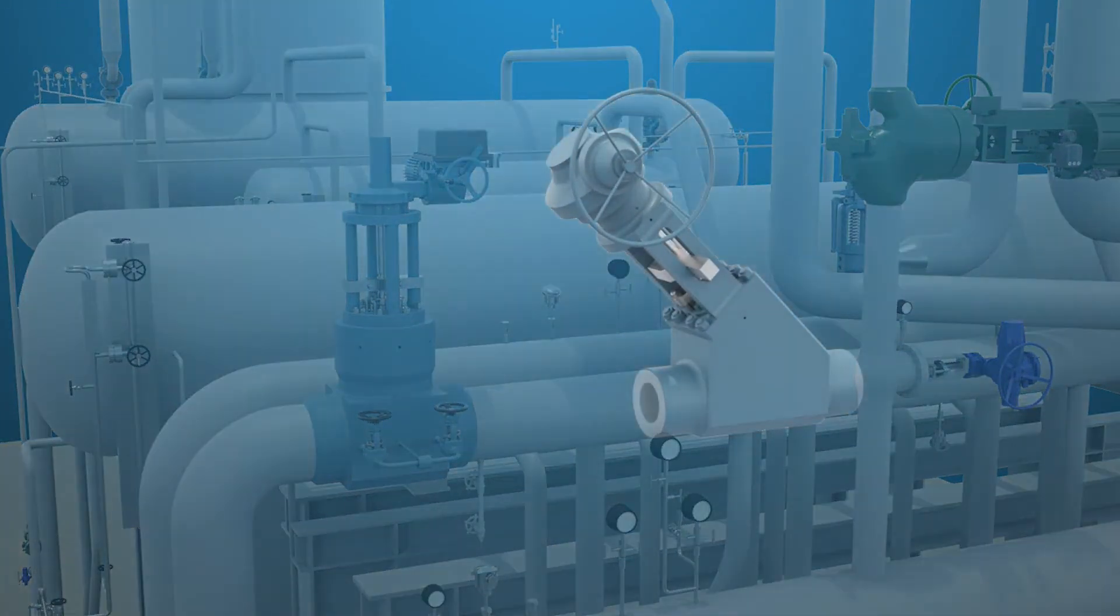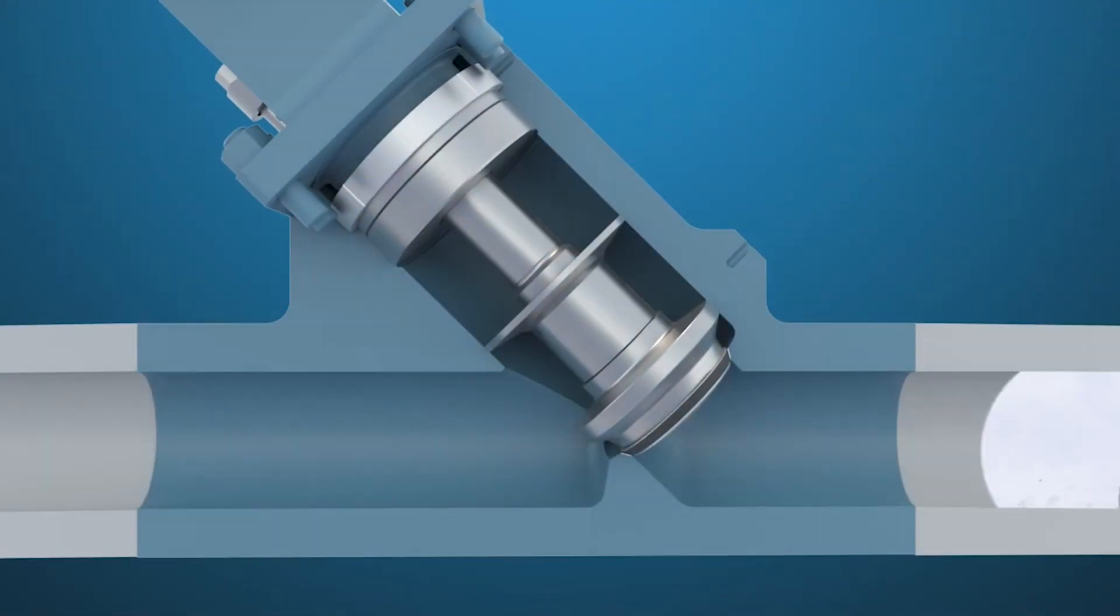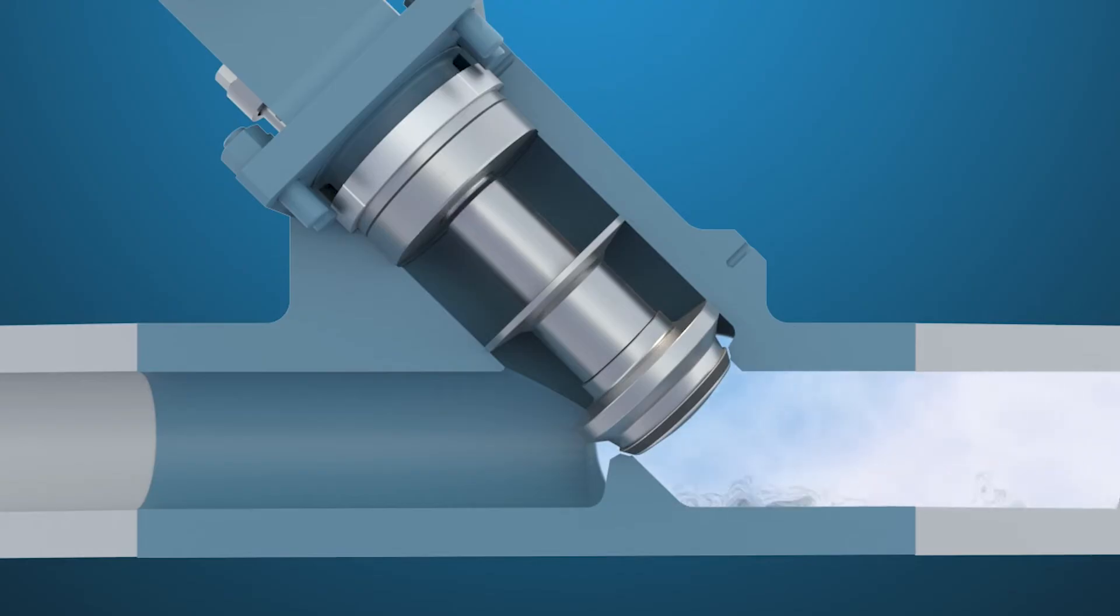The stop-check valve is used in power plants for safe operation of a HRSG. If a HRSG is offline or trips, the stop-check prevents the higher pressure from operating units to backflow into the offline HRSG. It combines the performance of an isolation and check valve into one unit.